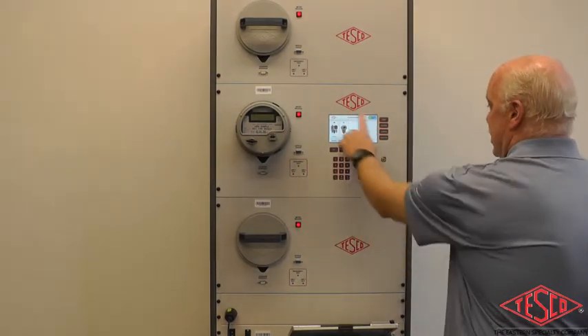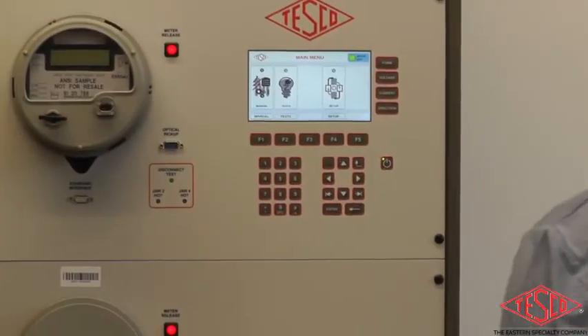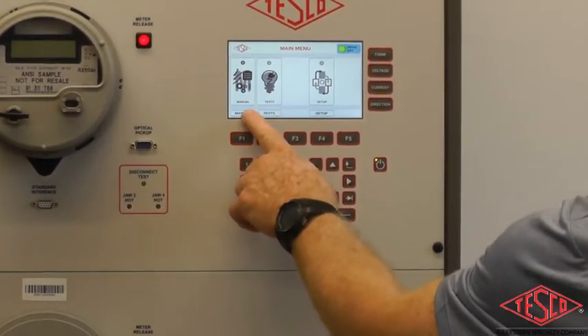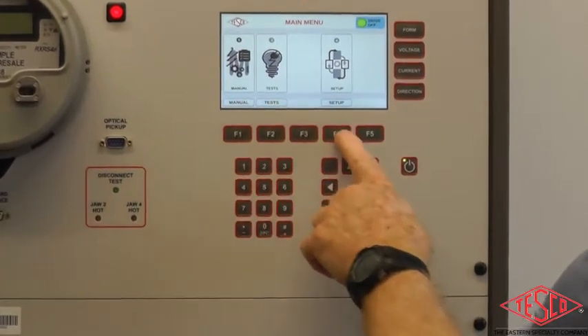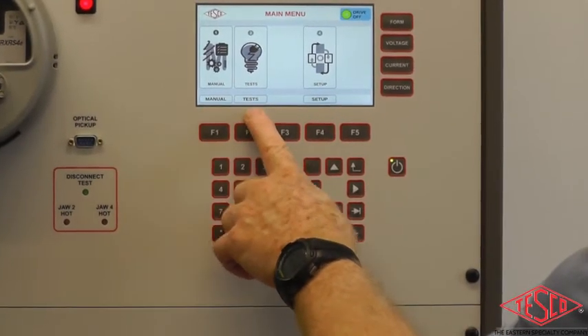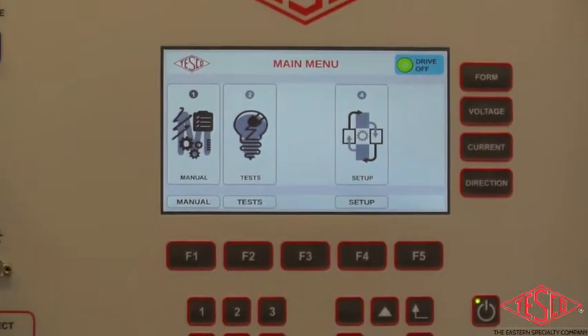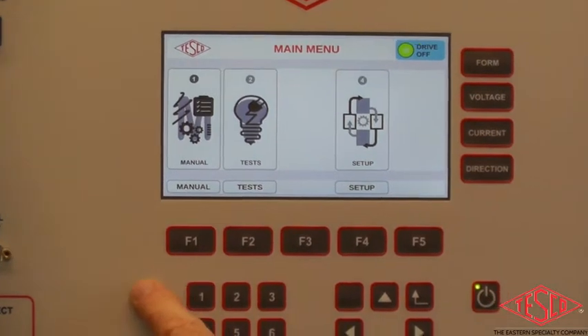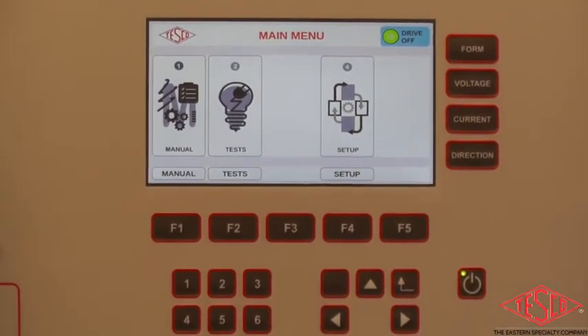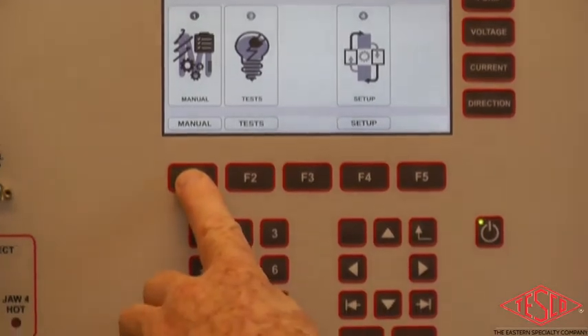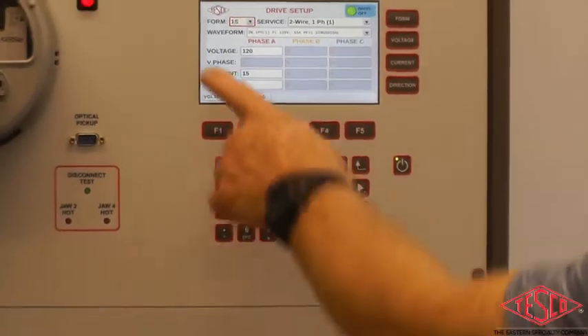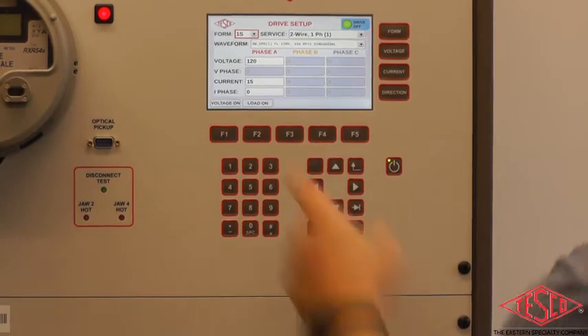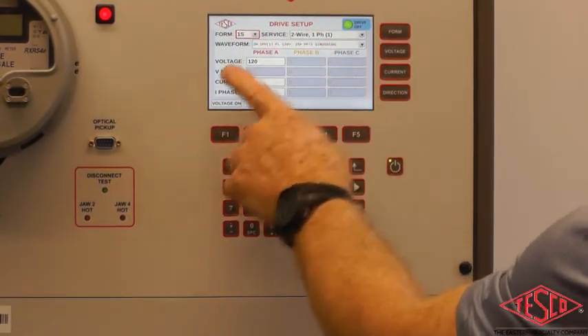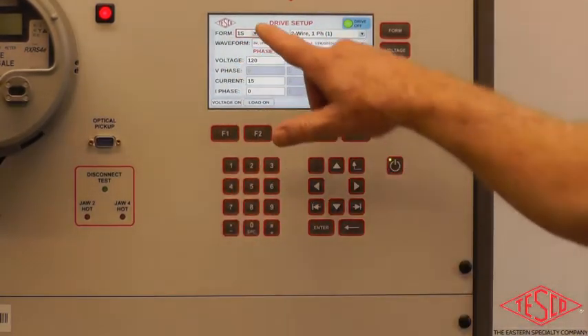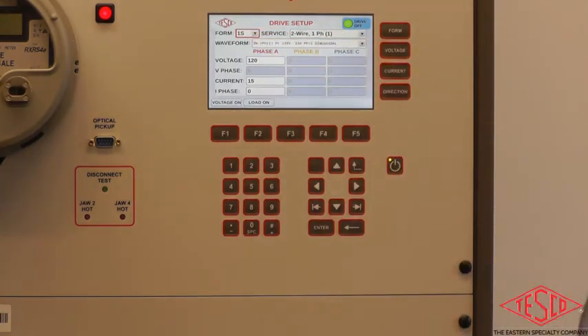Now you go to the main menu here, this is your main display, and these function keys here are correlated with various things. Here you have your manual drive screen, your test screen, and a setup screen where you can get information and do some calibration. So basically we're going to work from the manual test screen first. If you press F1, it'll go into the manual drive, and here you'll see all the different boxes for your meter form, your services, and the different voltages. Most of these are filled in automatically by form.